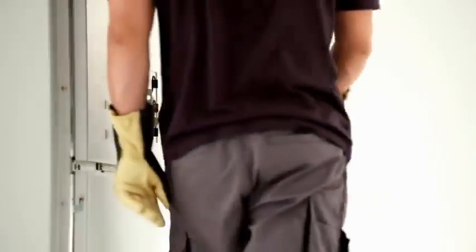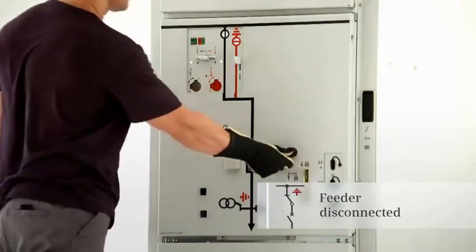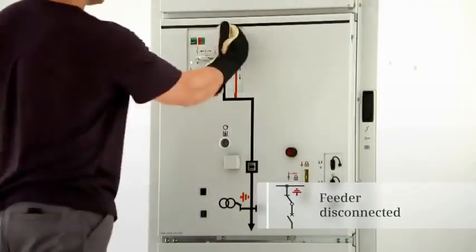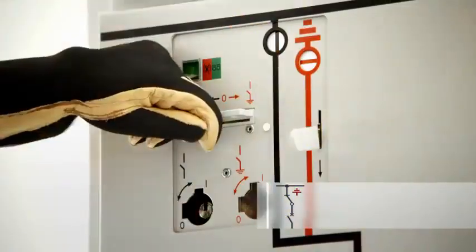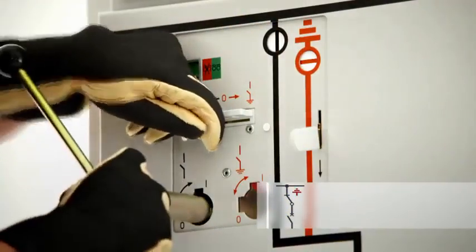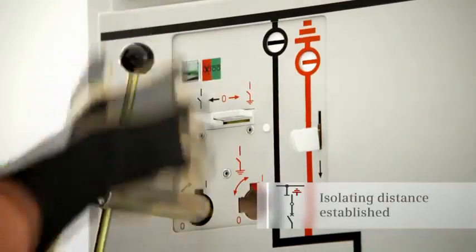To disconnect a feeder from the bus bar and to earth it subsequently, the circuit breaker is first switched to the open position. Only after the interrogation lever has been pushed down and the control gate has been pushed to the left can the three position disconnector be switched to the open position by turning the operating lever counterclockwise.